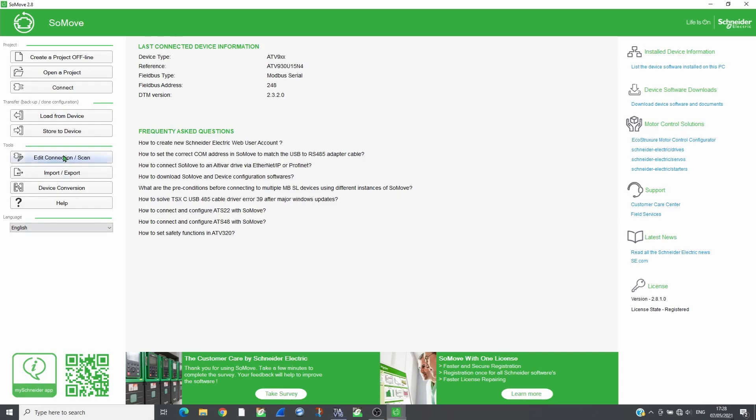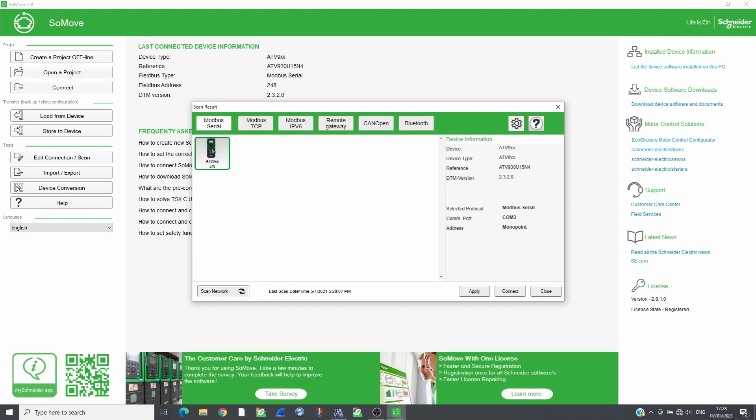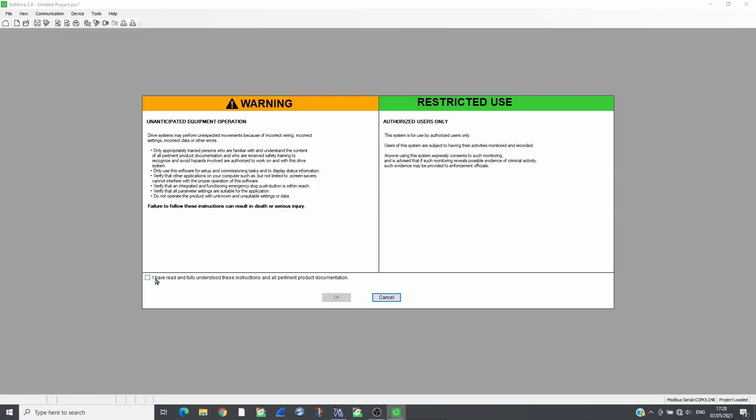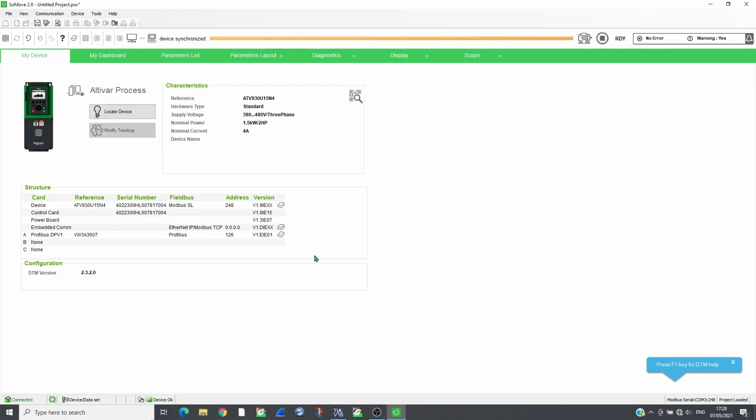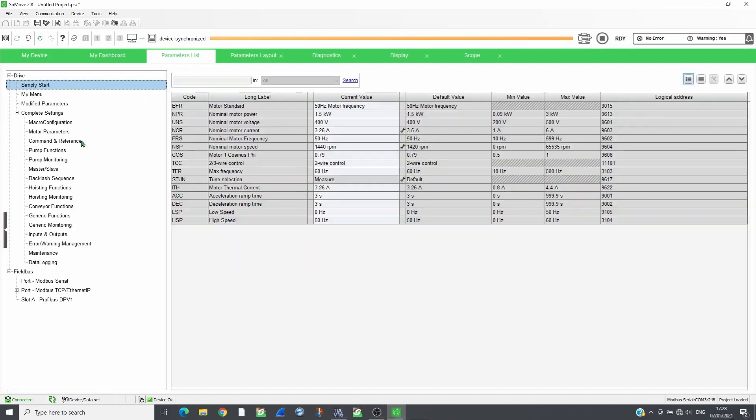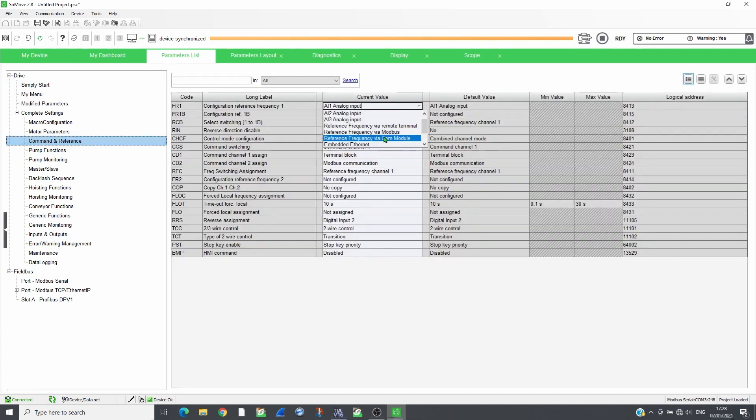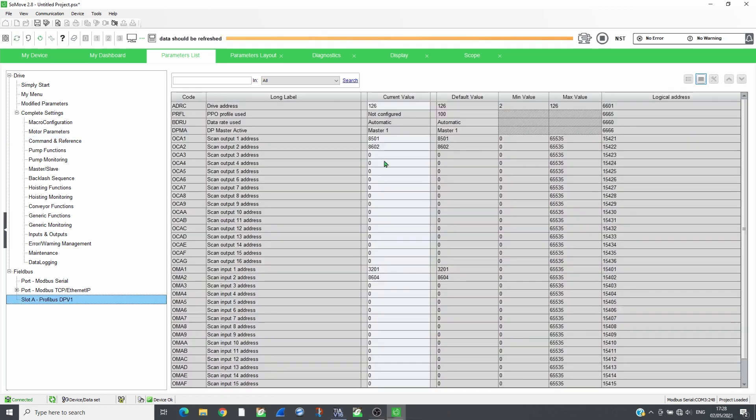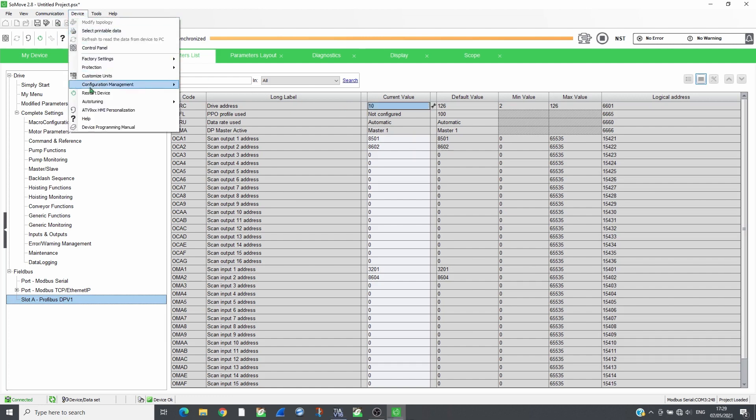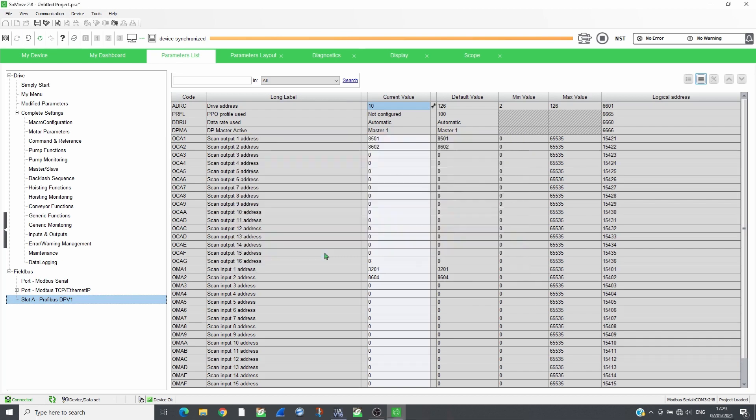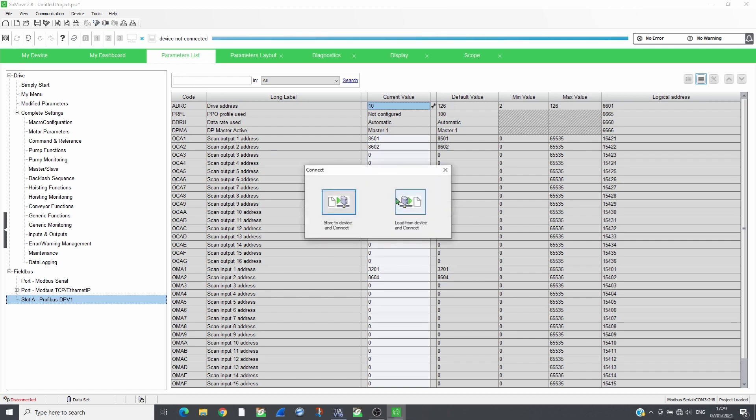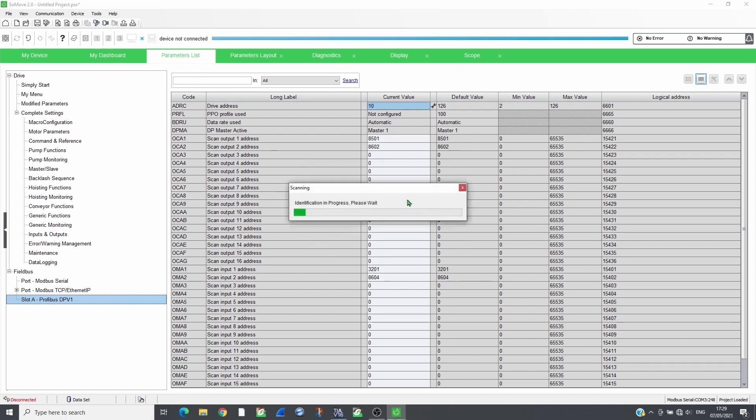Open SoMove and connect to the drive which has VW3A3607 plugged in. Set the reference and command channels to the communication module. The drive will be controlled following CIA402 profile. Set the PROFIBUS address and apply the changes, then restart the drive. Connect again to the drive and check that the parameters are saved.